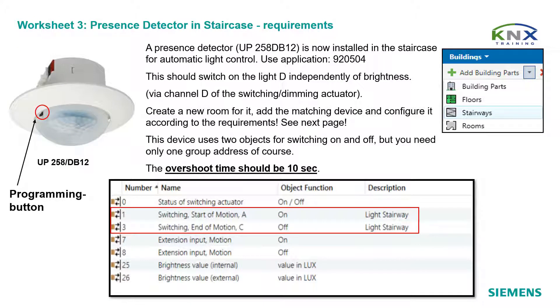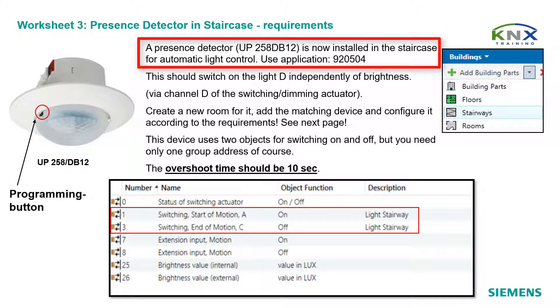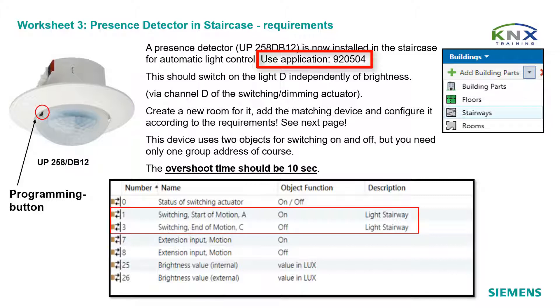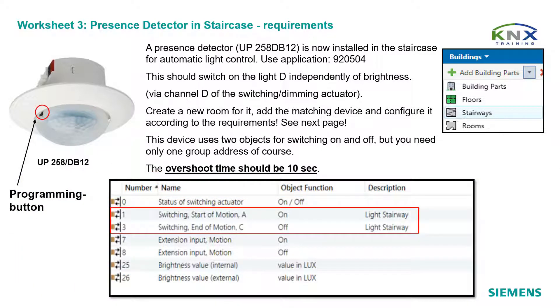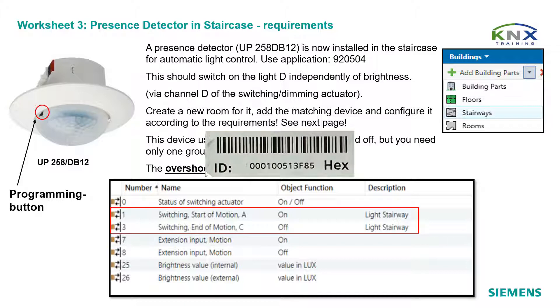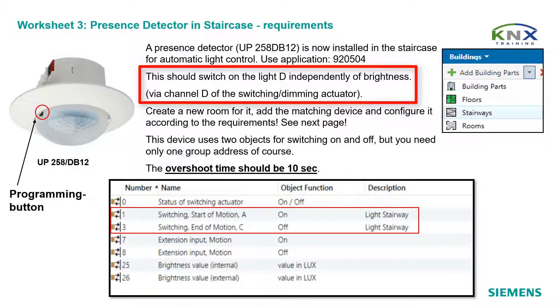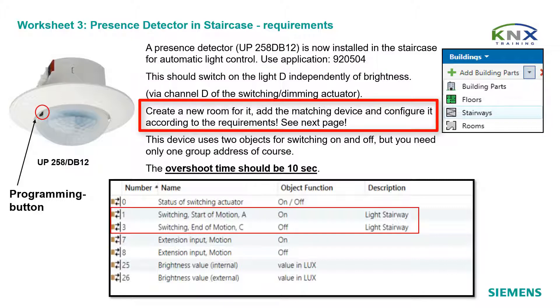Presence detector in staircase — requirements. A presence detector UP258DB12 is now installed in the staircase for automatic light control; use application 920504. As it is a new device, you have to download a new individual address — use number 13. Depending on how you can access the device, you can either press the programming button or use the serial code from the barcode sheet. Create a new room for it: the staircase.